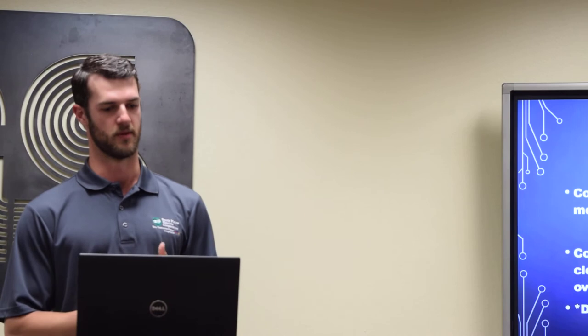Coordination. The big idea that we go for is that the fewest number of members are out during an outage that you don't have a whole line out when it's just one dude doing something. Current device sizing is important so things are clear quickly. But the secondary thing is that coordination is a domino effect. If you make a transformer big and you have to have a big fuse, you have to have a big recloser, big recloser, big substation setting. So we really try to keep things as on the mark as we can when we're doing this from the transformer sizing all the way back to the substation because if one of them bumps, the rest of them have to bump. That's kind of the dance that we do.